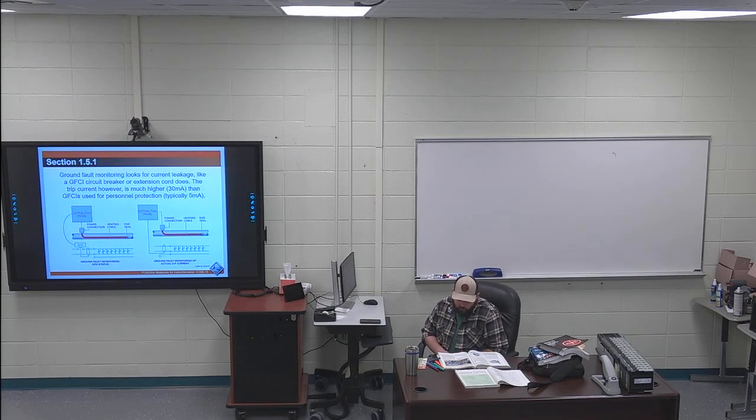Heat tracing system monitoring. So this is monitoring the system as a whole. Ground fault monitoring, 151 on page 9. Last paragraph on page 9, second sentence is highlighted. However, the function of the equipment ground fault circuit breakers is to protect the equipment rather than personnel.